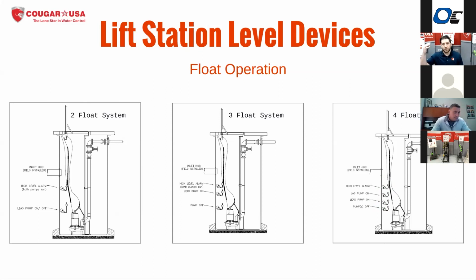The only concern here is that you won't get your high level alarm until both pumps can't keep up. So when we go through the demo on here, I'll show you we have a lag pump counter that will keep track of how many times your lag pump has come on and can give you an alarm to let you know that it keeps coming on. Okay. Was there a question in the Q&A?